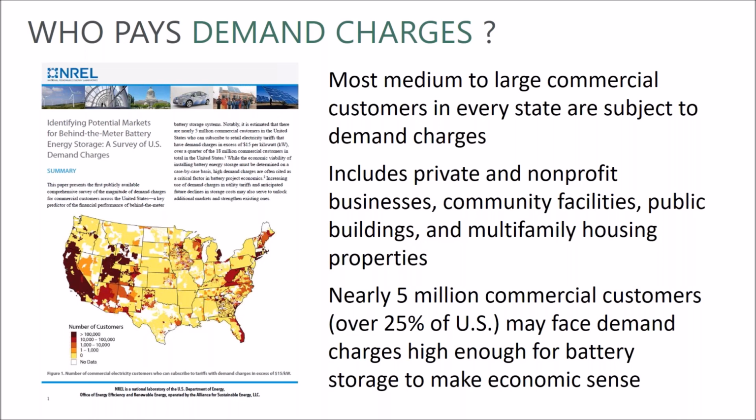We did a report with the National Renewable Energy Laboratory that surveyed over 10,000 utility rates across the country, and they found that nearly 5 million commercial customers could be subscribed to a rate tariff that had demand charges high enough where energy storage could start to make economic sense. Typically, we found around $15 per kilowatt. It doesn't mean that it will make sense, but it's just the beginning stage of where we've found it might make sense to look at it.